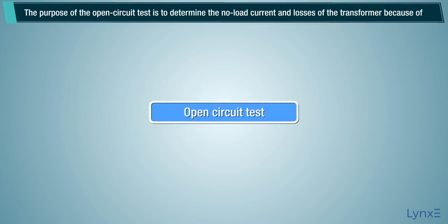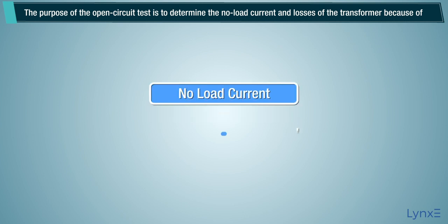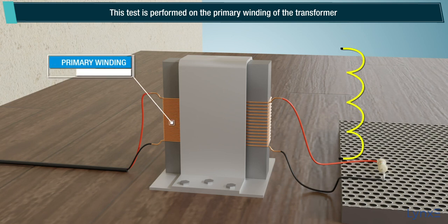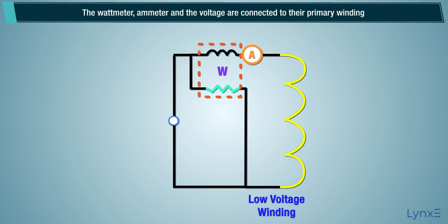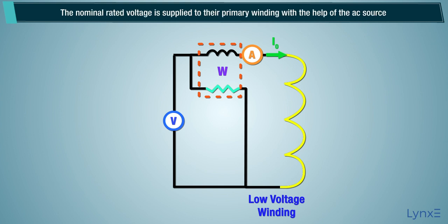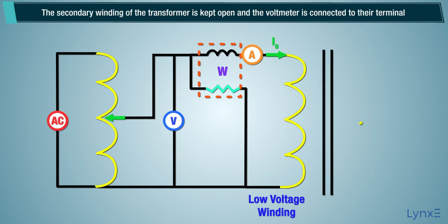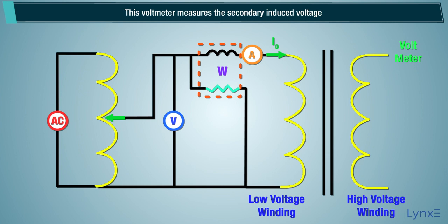The purpose of the open circuit test is to determine the no-load current and losses of the transformer, because of which their no-load parameters are determined. This test is performed on the primary winding of the transformer. The wattmeter, ammeter, and voltmeter are connected to the primary winding. The nominal rated voltage is supplied to the primary winding with the help of the AC source. The secondary winding of the transformer is kept open, and the voltmeter is connected to their terminal. This voltmeter measures the secondary induced voltage.